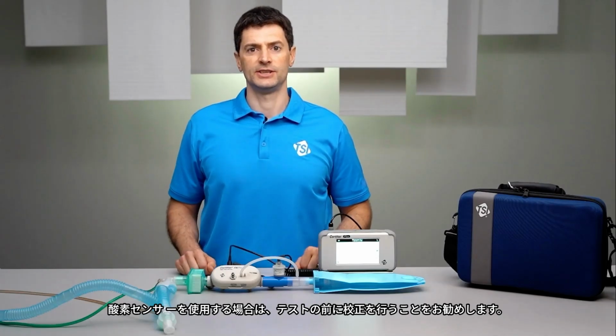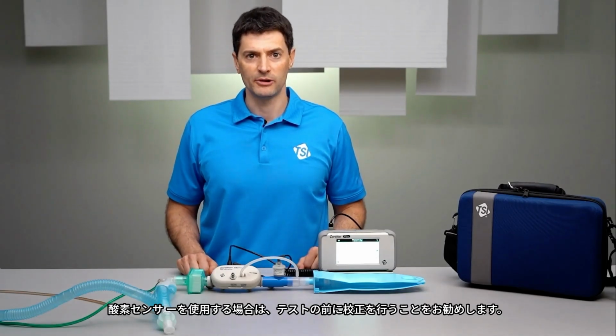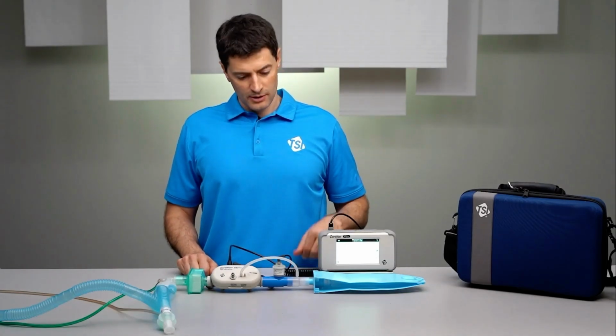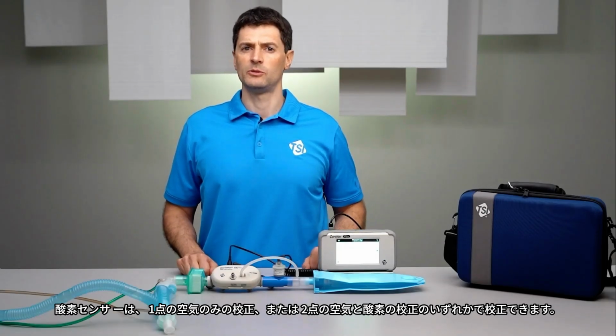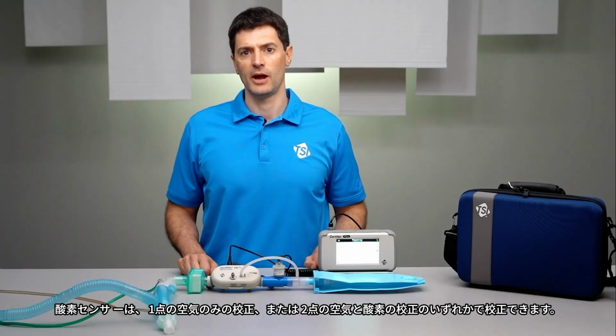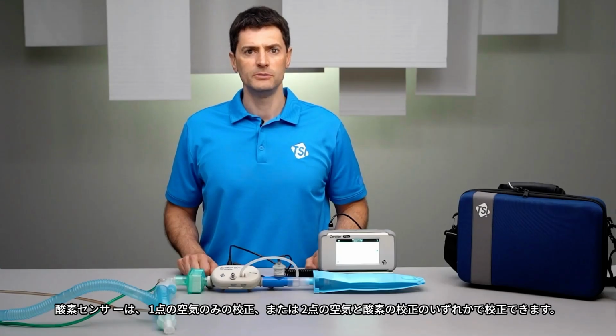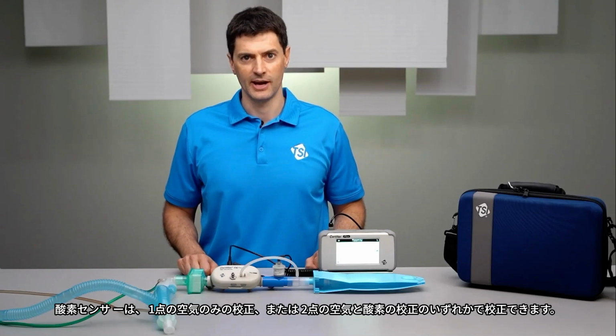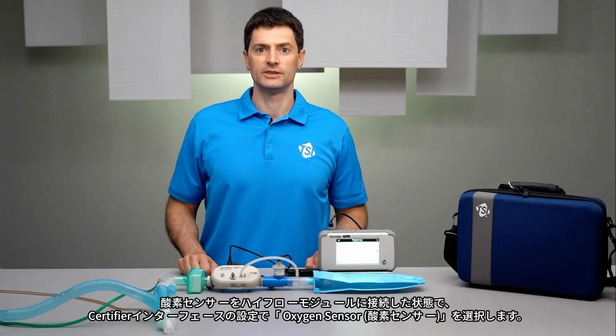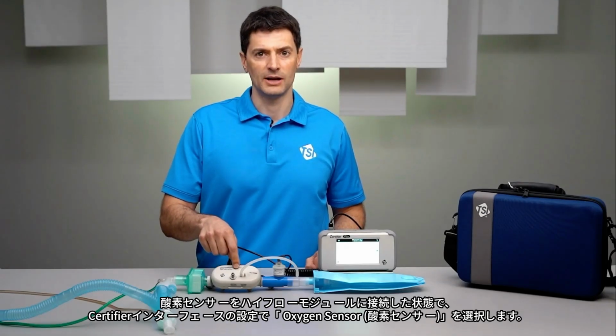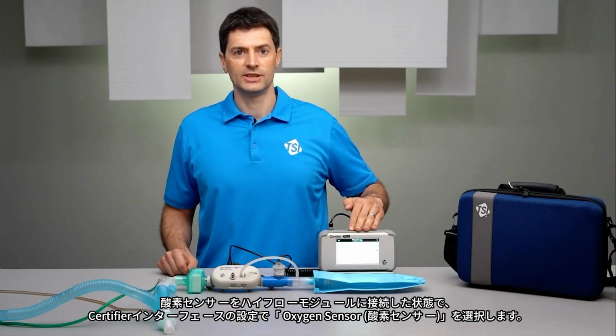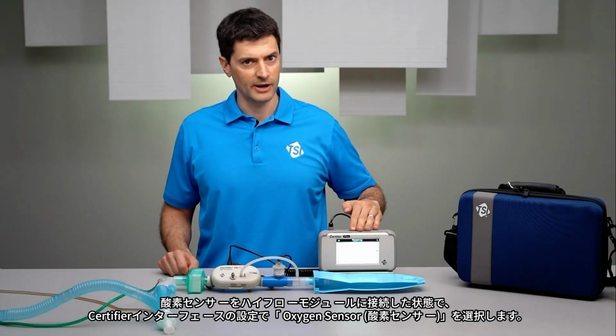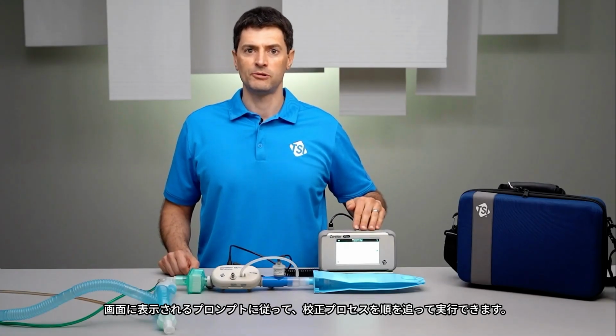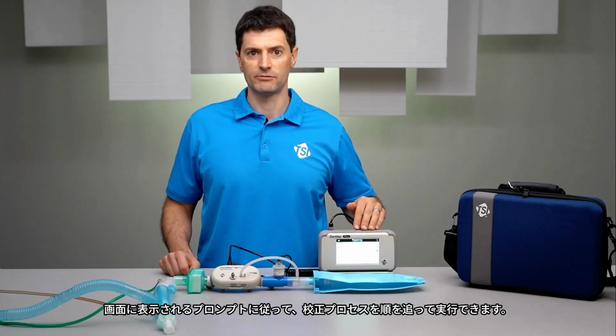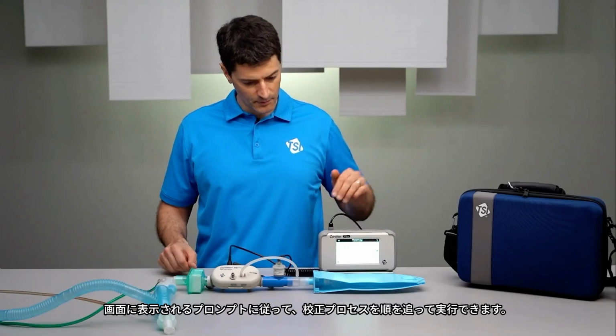If using an oxygen sensor, it's recommended that you calibrate it before testing. The oxygen sensor can be calibrated with either a 1-point air-only calibration or a 2-point air and oxygen calibration. With the oxygen sensor connected to the high flow module, select Oxygen Sensor in the settings of the Certifier interface, and the on-screen prompts will take you step by step through the calibration process.